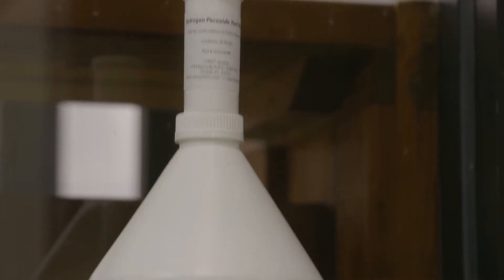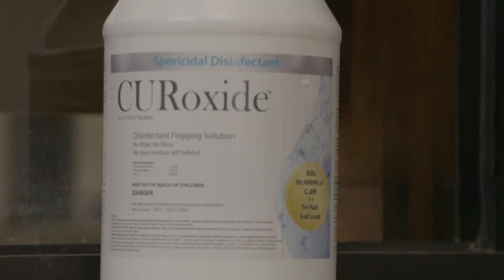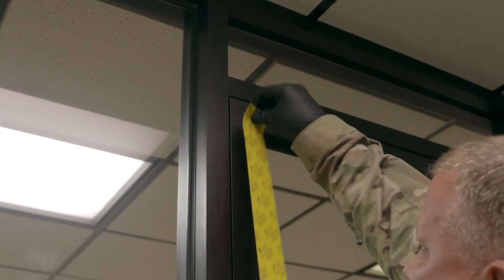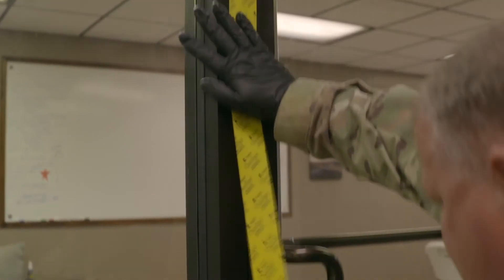The hydrogen peroxide solution is 7% hydrogen peroxide and 93% water vapor. The machine runs on square footage — we set the ductwork square footage on the machine, and it will run for possibly 30 to 40 minutes. It has to allow for contact time on that virus to kill it.